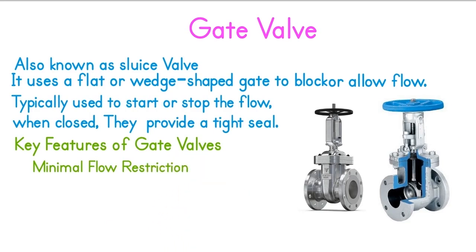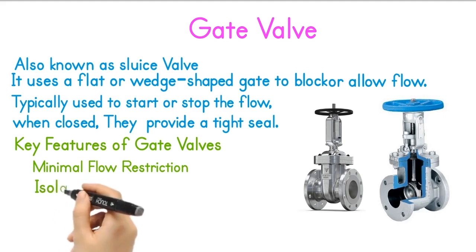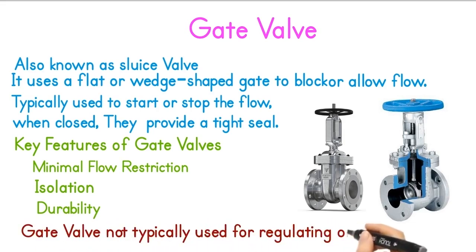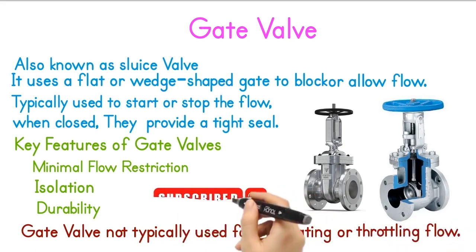When fully open, gate valves provide minimal resistance to flow, making them ideal for applications where free flow is needed. They are commonly used for isolating portions of a pipeline, preventing or permitting flow to specific areas. They are designed for high-pressure and high-temperature environments, found in industries like oil and gas, water treatment, and power plants. Gate valves are not typically used for regulating or throttling flow, as they can cause turbulence and damage when partially open.